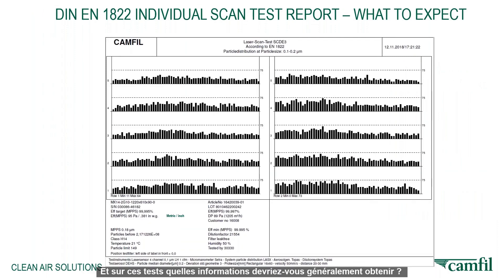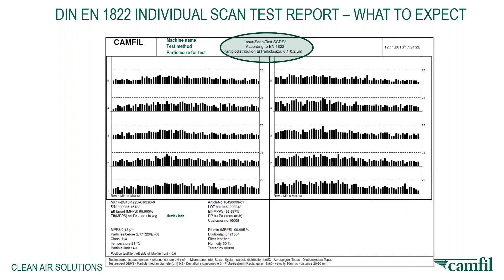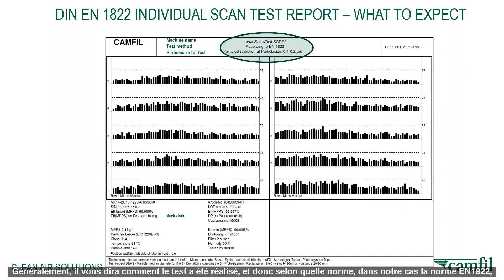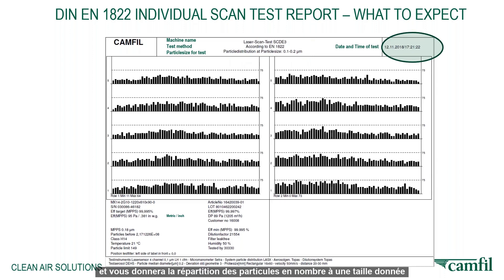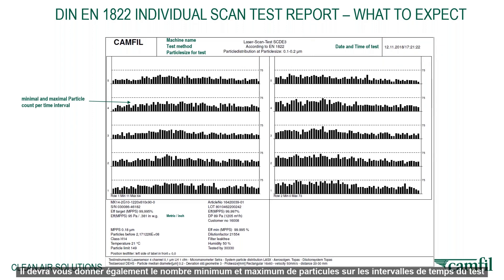On those test certificates, what should you typically get? It must tell you how the test was carried out — so according to what standard, in this case EN1822 — the type of equipment used, the laser scan test, and a particle distribution at a number of particle sizes. It must give you the date and time of the test, where and when it was carried out, and the minimum and maximum particle count over the time intervals of the test.